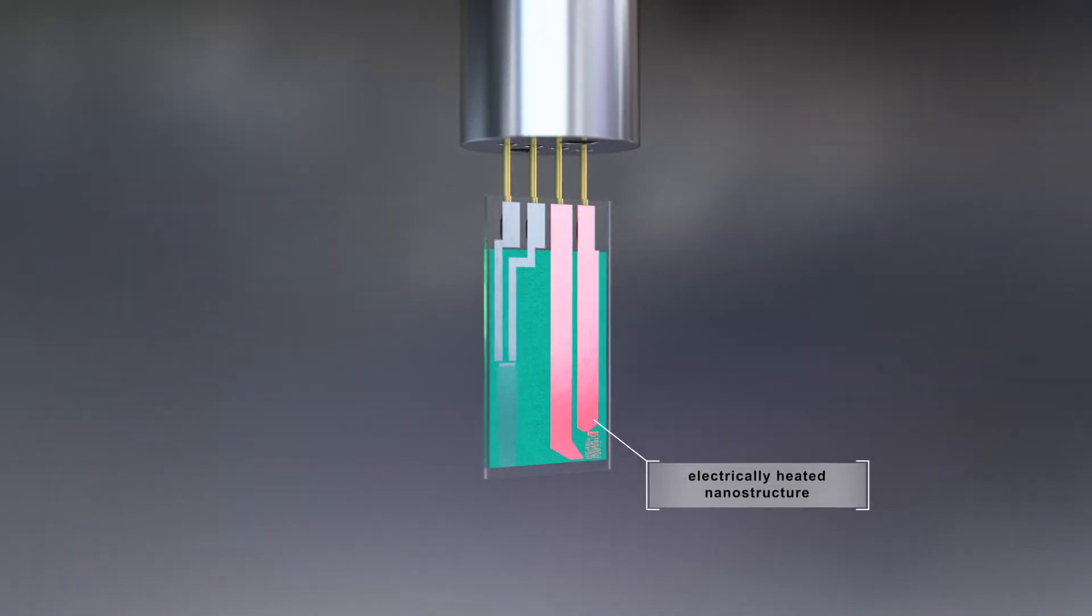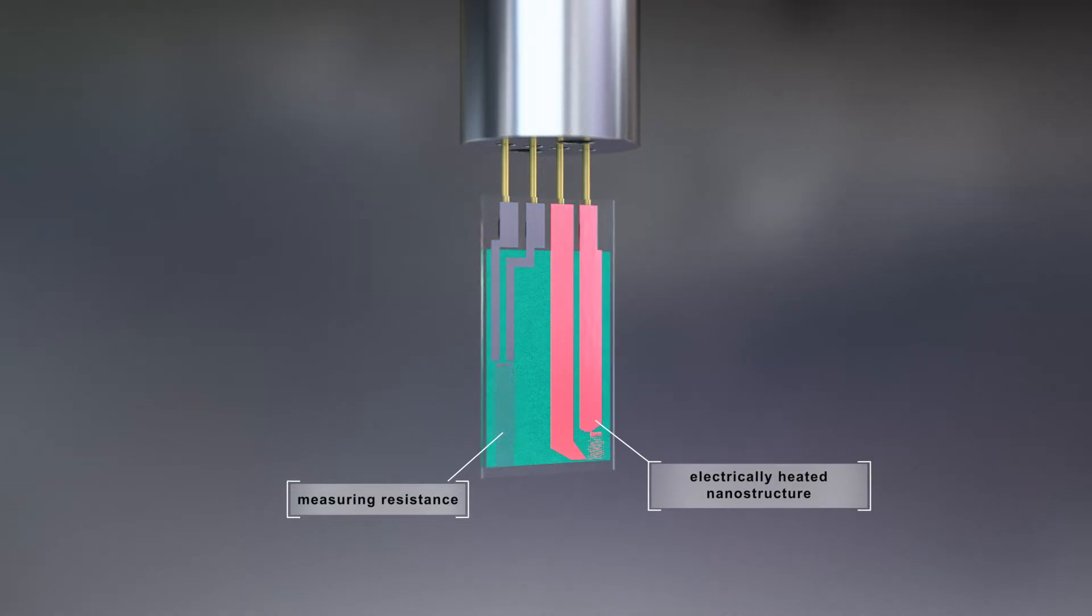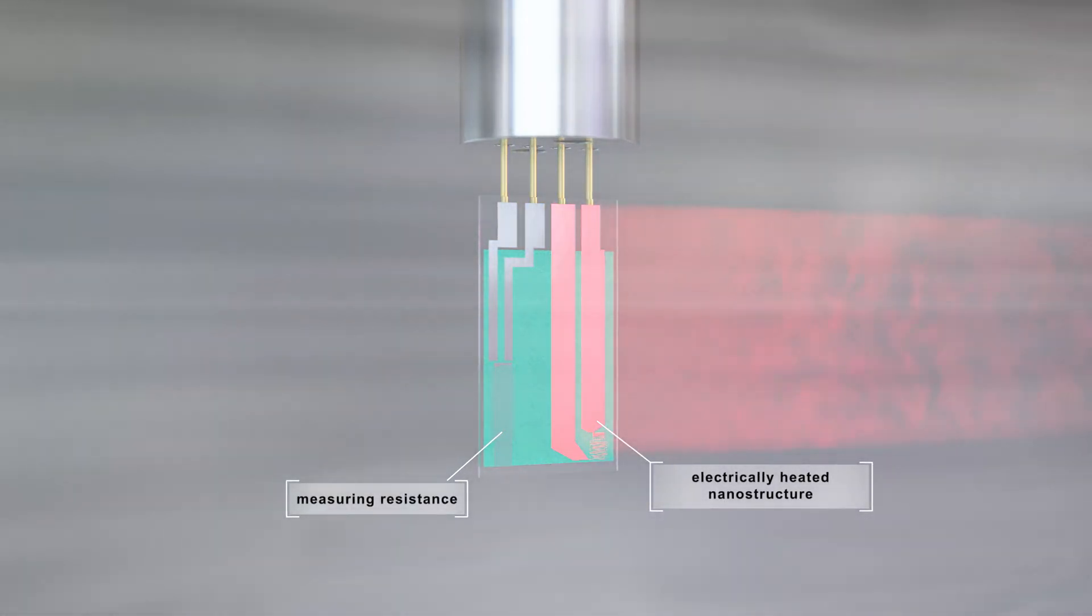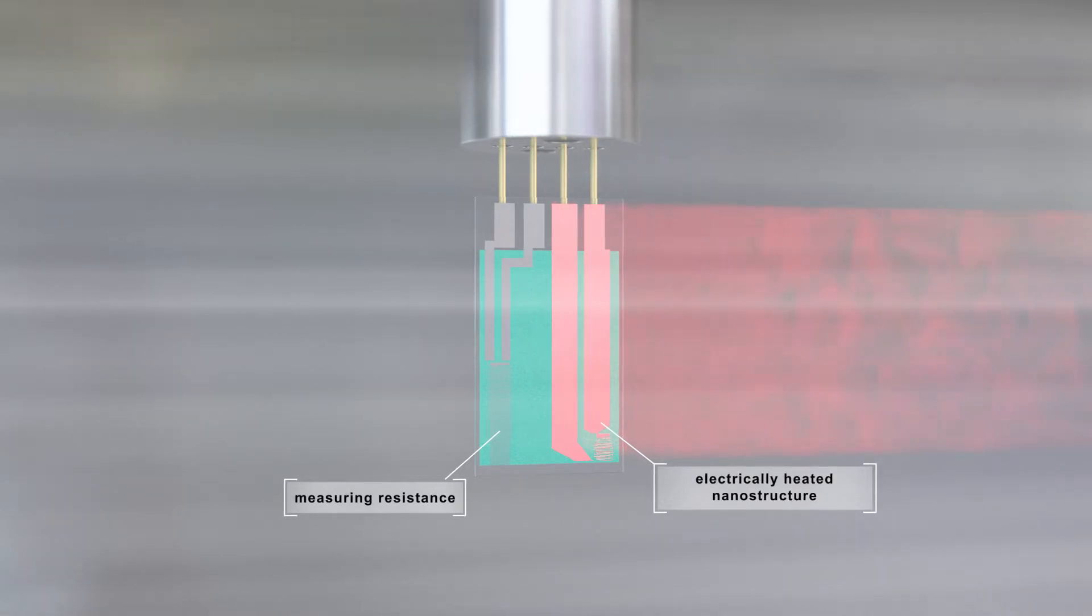Additionally to the electrically heated nanostructure, there is a second resistor layer. The faster a medium flows over the heated sensor element, the more heat it conveys. The change in resistance caused by the cooling is proportional to the mass flow of the medium.